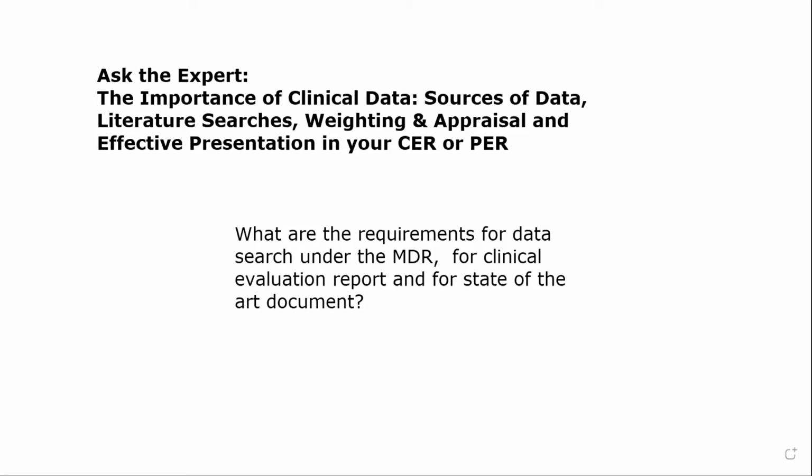Now, to answer the question, what are the requirements for the data searches? For the clinical evaluation report, we always say there are 3 searches that need to be performed for a CER. One is on the competitor devices, one is on the subject device, and one is to help inform the state-of-the-art story. So I'll start with that one.